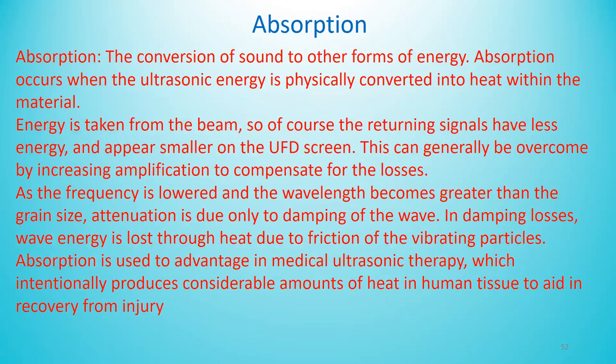Absorption is the conversion of sound to other forms of energy. Sound is absorbed into heat energy, physically converted to heat within the material. Energy is taken from the beam, so of course the returning signal has less energy and appears smaller on the UFD screen. This can generally be overcome by increasing the amplification to compensate for the losses.